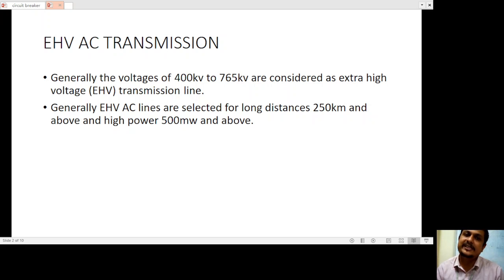So the major advantage is that it reduces transmission losses. In EHV transmission, voltage ranges from 400 kV to 765 kV, generally considered extra high voltage. This is for AC transmission systems, and most transmission networks nowadays in our country use AC. Generally, EHV AC lines are selected for long distances above 250 kilometers and higher power above 500 megawatts.